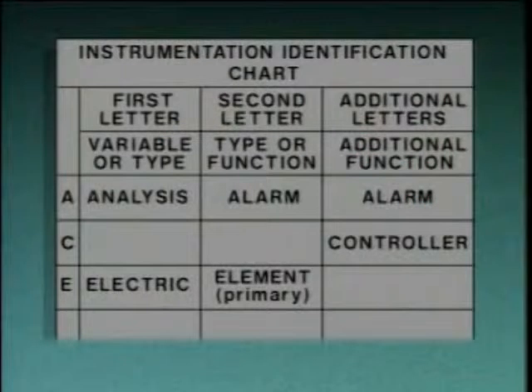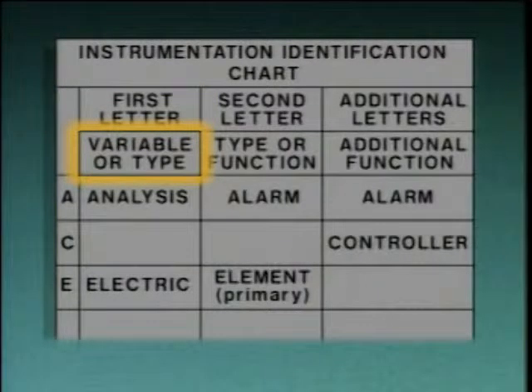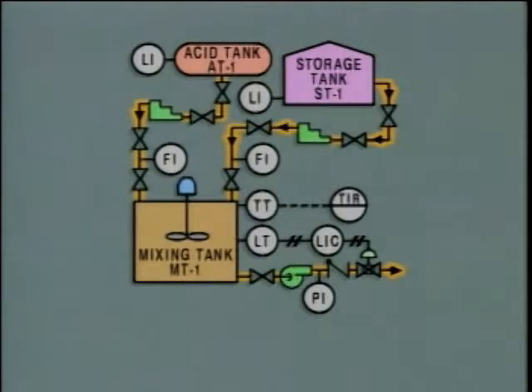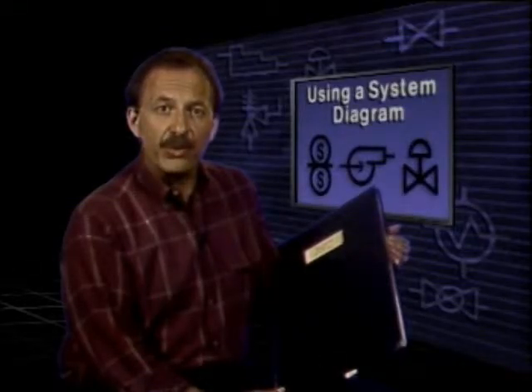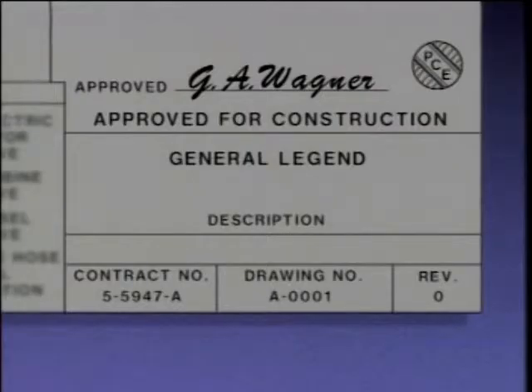This is the diagram we'll be working with. We'll start at acid tank AT1. There is only one instrument symbol shown for the acid tank. The symbol containing the letters LI represents a locally mounted level indicator that shows how much acid there is in the tank. Storage tank ST1 also has a local level indicator. The symbols for equipment and instruments on a P&ID are connected by lines, but the lines aren't all the same. Solid lines typically represent process piping or instrument connections to the process. Lines with slashes usually represent pneumatic signal lines, and dashed lines typically represent electrical signal lines.